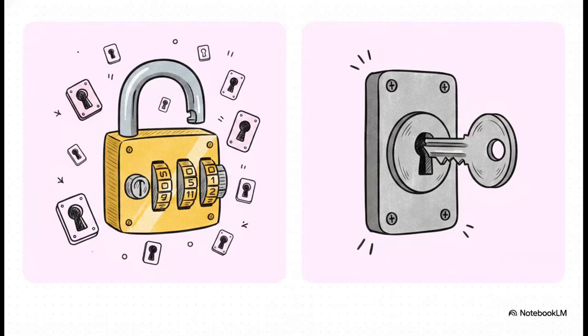I like to think of low impedance REF as an adjustable combination lock. You can reprogram the software to fit almost any door, or in our case, any weird set of mismatched CTs you happen to inherit. High impedance REF, though, that's a fixed key deadbolt. It only works on one exact lock. Sure, it's way less flexible, but for that one specific door, literally nothing beats how secure and stable it is.